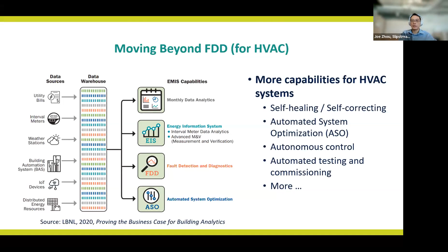Now we're moving beyond FDD for HVAC systems, adding more capabilities. The next few panels will talk about how we can make the system self-recovering, self-healing, or self-correcting. Whether you detect faults or detect a bias on the sensors, the system can self-correct those and become autonomous in control, or the software can do the static pressure reset automatically without you retrofitting the actual system. So automated system optimization can do that, and we can also move beyond FDD so that the system can do automated testing and commissioning and more. The next several panels will talk more about these capabilities on the HVAC system.